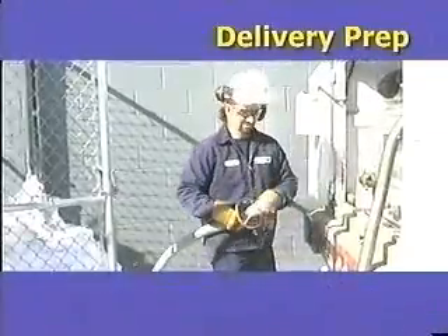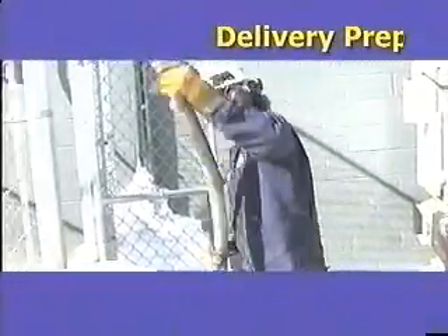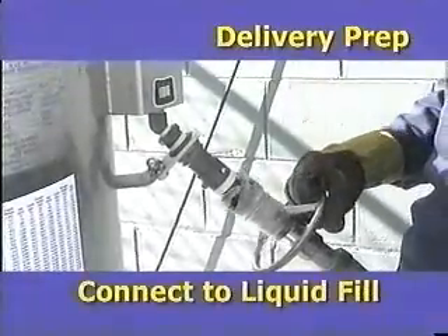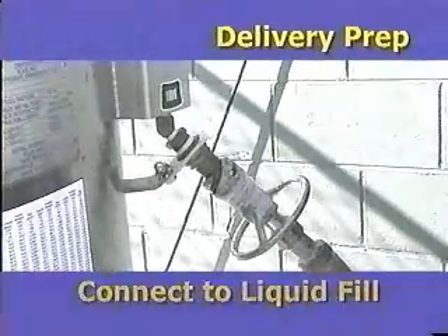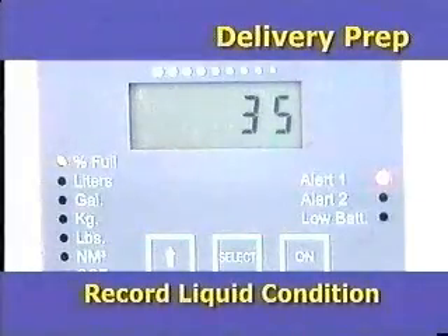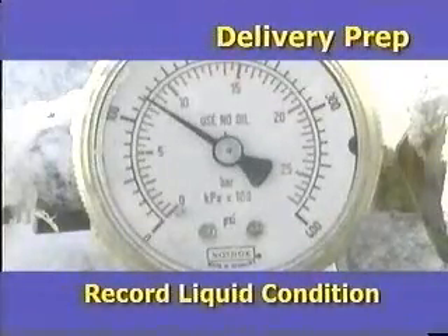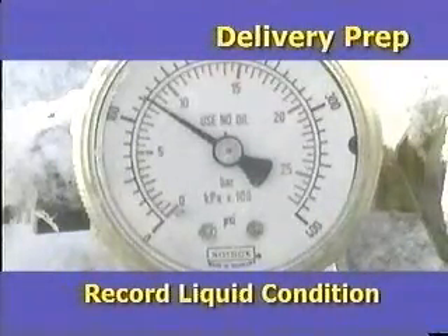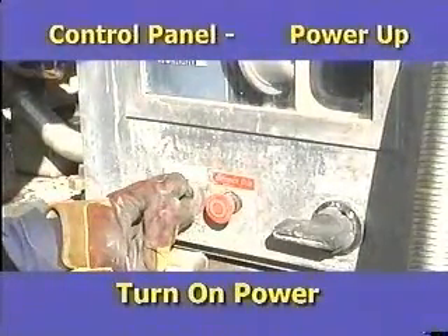Remove the delivery hose, inspect and prep the fill connection. Connect the hose to the fill connection on the Perma-Cyl. Record the initial liquid level condition on the Perma-Cyl and the initial Perma-Cyl pressure. Next, on the Orca control panel, power up the 12-volt DC.